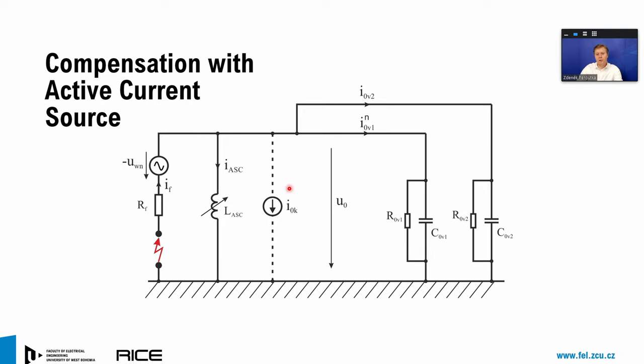The problem is how to calculate the compensation current, which behaves based on the first Kirchhoff's law. It means that if we are able to produce a compensation current which has the same magnitude as the fault current but opposite phase, then we will be able to mitigate the fault current and fully compensate the ground fault in the power grid.